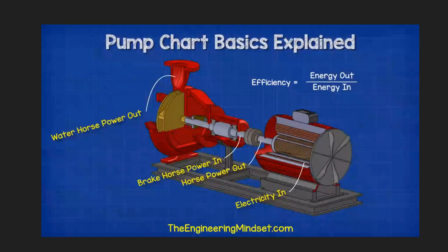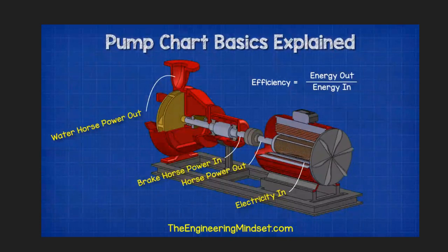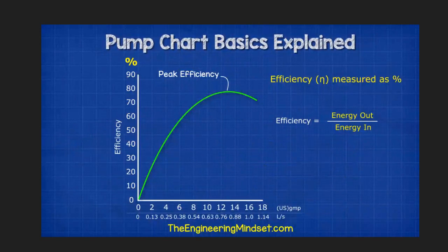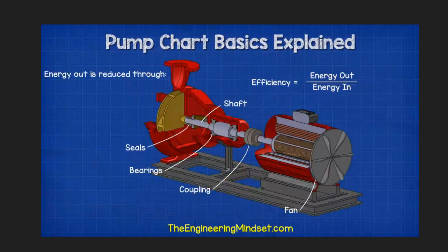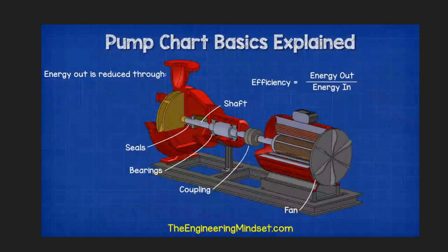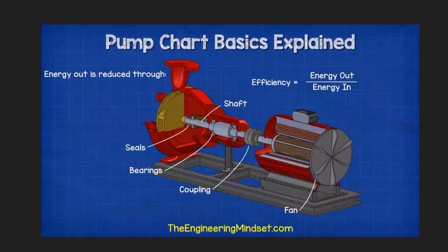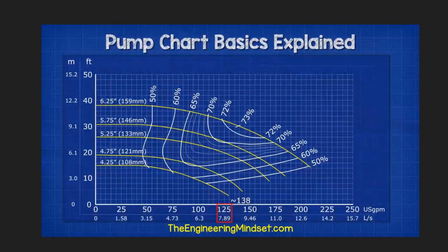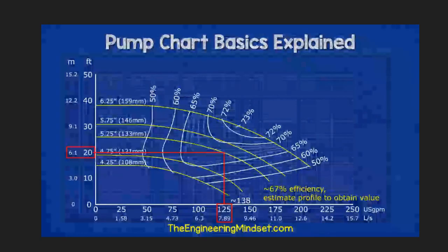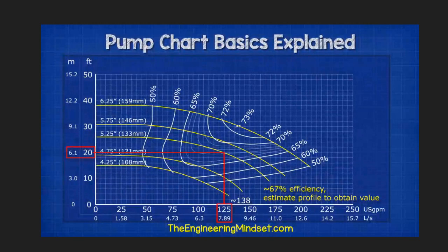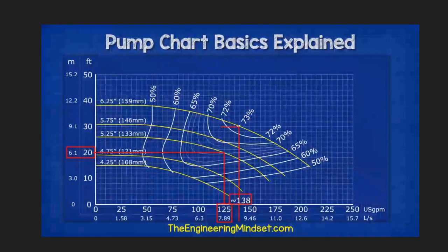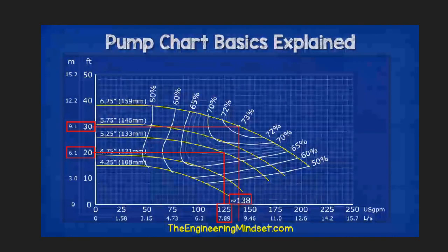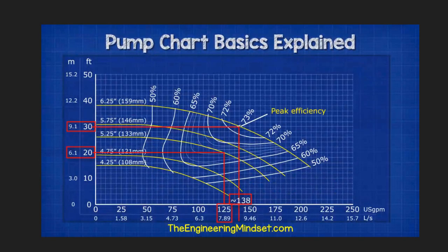Efficiency is the ratio between the amount of energy going into the pump versus the amount of energy we get out. Ideally we want this to be as close as possible to the peak for optimal performance. The pump will always lose some power when converting electrical energy into mechanical energy, lost through the couplings, bearings, shaft, seals, cooling fan, etc. For example, if the pump provided 125 gallons per minute at 20 feet of head, it would run at around 67% efficiency. If the same pump operated at 30 feet of head for 138 gallons per minute, it would operate at its peak performance of 73%.